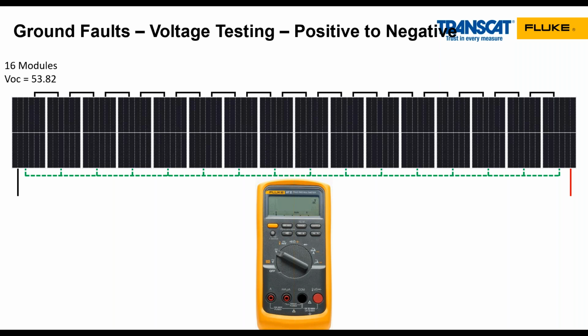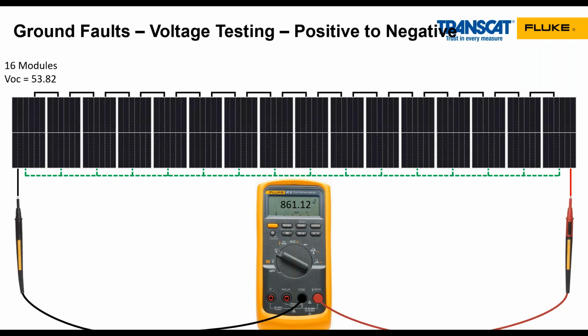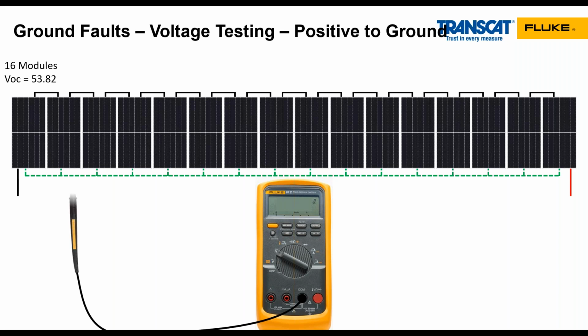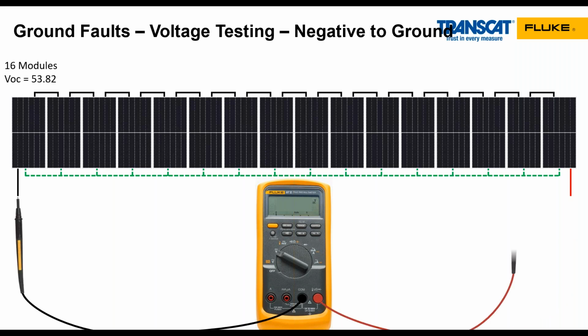I've got 16 modules, open circuit voltage is around 53 volts. If I measure from negative to positive, I should get the open circuit voltage of the string, approximately 861 volts. If I now measure from the ground to the positive, I should get 0, but in this case I got 645 volts. I'm going to document that, write it down. If I test between my negative and ground, I should get 0. In this case I got around 215 volts. Again, I will document that, write it down.